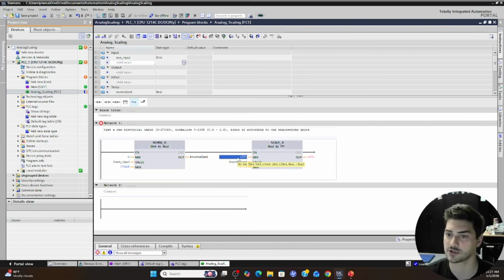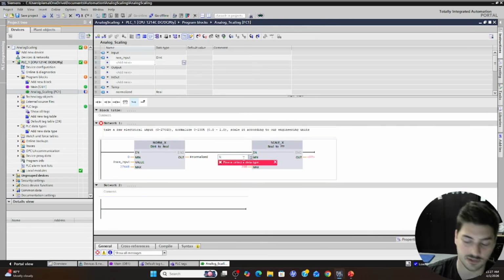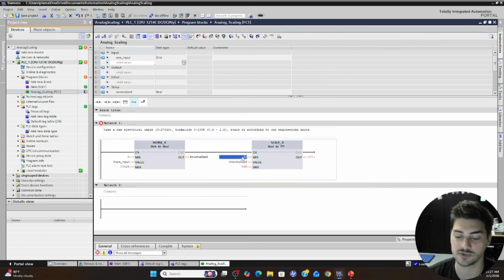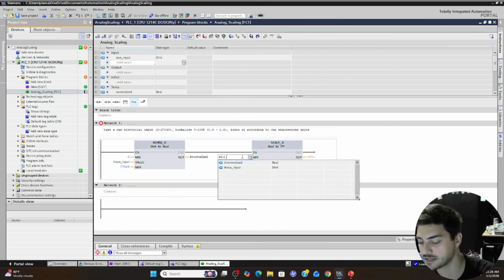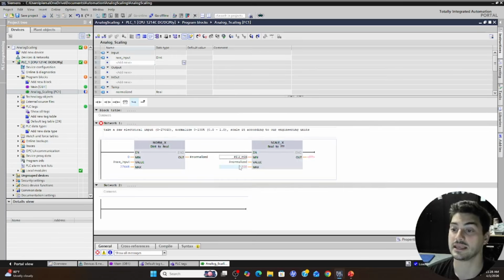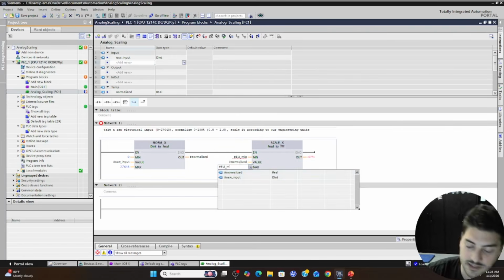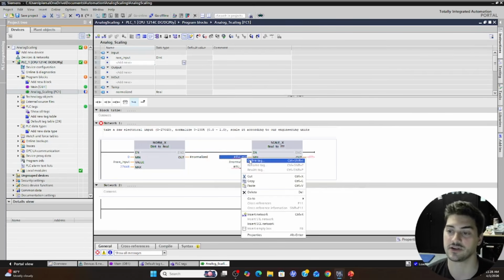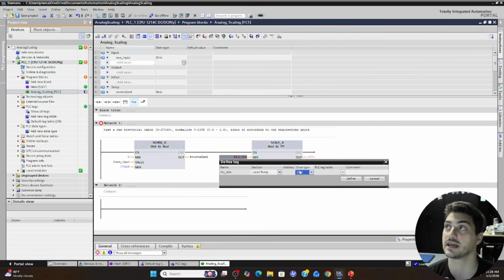If you're measuring the temperature of a liquid, a lot of these are scaled to like 32, or they'll be 32 to 200, but you want this function to work if you get another temperature sensor that goes 50 to 300. So again, to make this reusable, what we want to do is make some new variables and call them EU min and EU max. You can call these something else that makes more sense to you. EU means engineering units, right? This means basically the actual range you want your scaled output to display as.